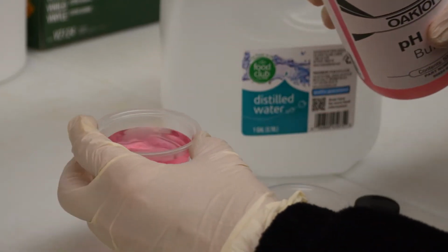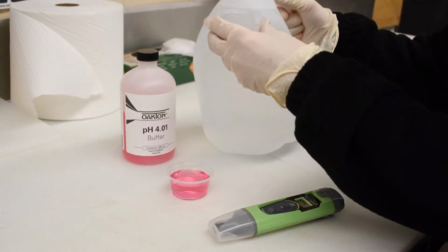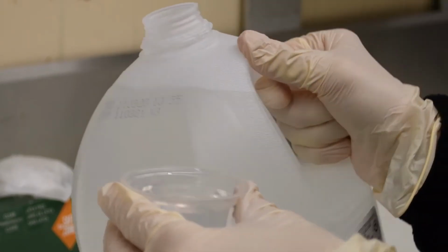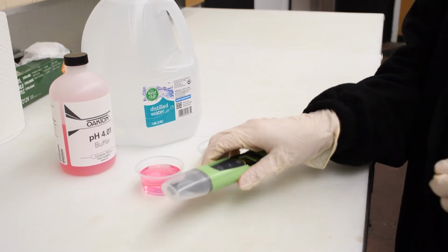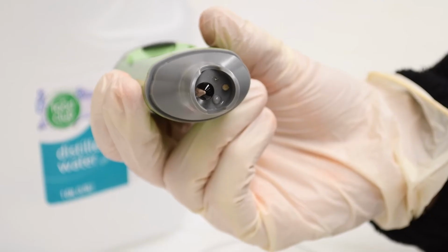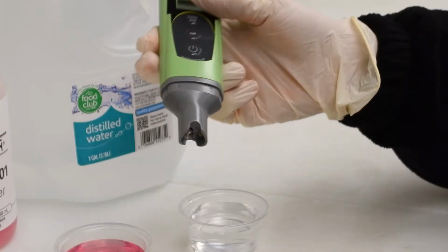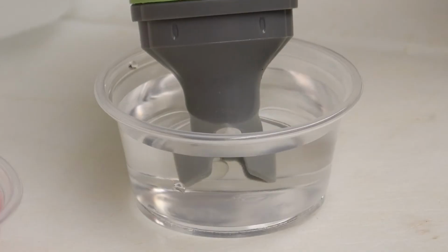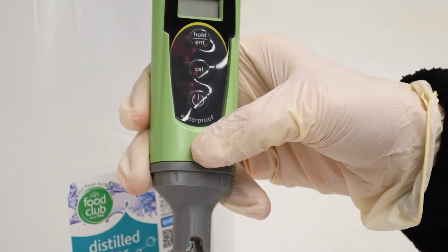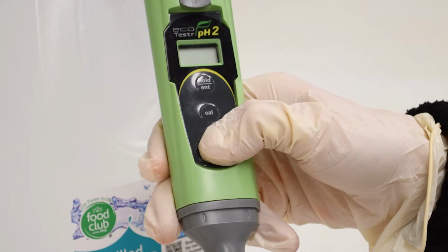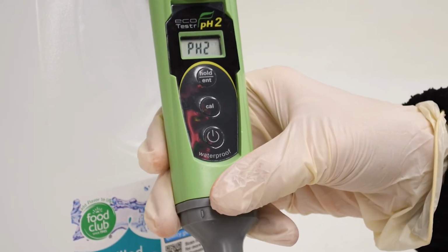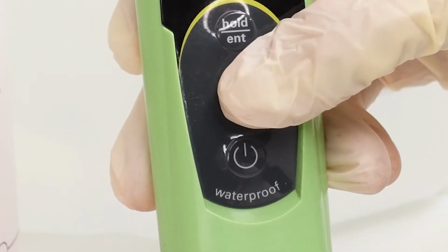Now, open and pour the buffer solution into a small portion cup and then the distilled water into another small portion cup. Remove the protective cover over the end of the pH meter and place the bulb sensor in the distilled water for approximately 15 seconds. Remove the meter from the distilled water and then turn on the pH meter. When ready, press the CAL button to calibrate.